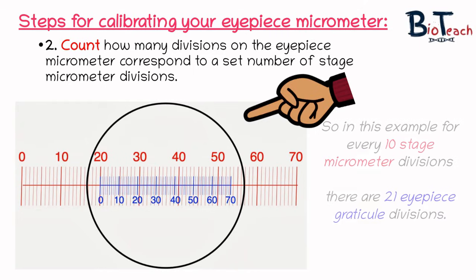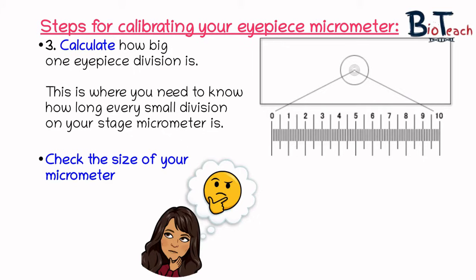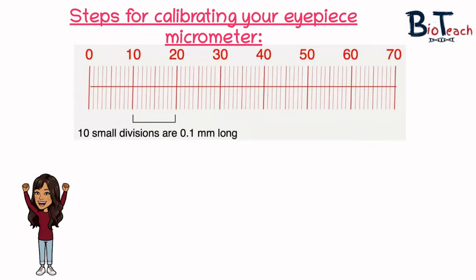In this example, the stage scale is shown in red and the eyepiece scale is in blue. You can see that every 10 stage micrometer divisions correspond to around 21 eyepiece graticule divisions. The next step is to calculate how big one division is on the eyepiece. For this, we need to know how long each small division is on the stage micrometer — you can check this by looking at the label on the slide itself. If it is one millimeter long in total, then every 10 small divisions is 0.1 millimeters, and every small division is 0.01 millimeters. This close-up scale illustrates that.